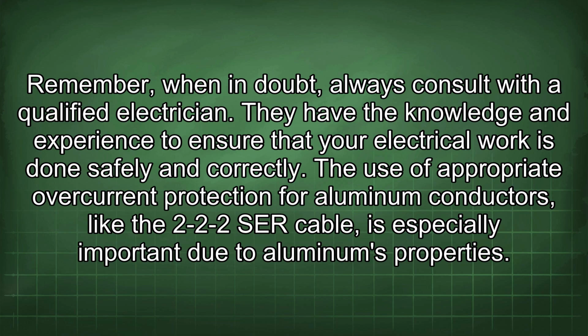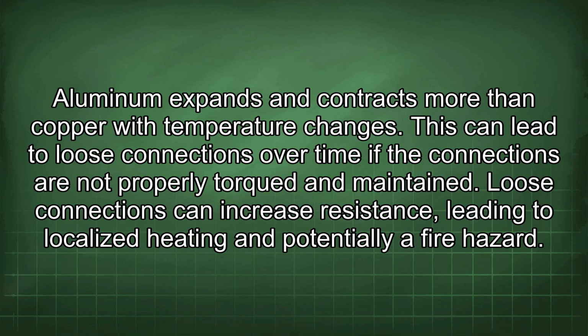The use of appropriate overcurrent protection for aluminum conductors, like the 2-2-2 SER cable, is especially important due to aluminum's properties. Aluminum expands and contracts more than copper with temperature changes. This can lead to loose connections over time if the connections are not properly torqued and maintained. Loose connections can increase resistance, leading to localized heating and potentially a fire hazard.